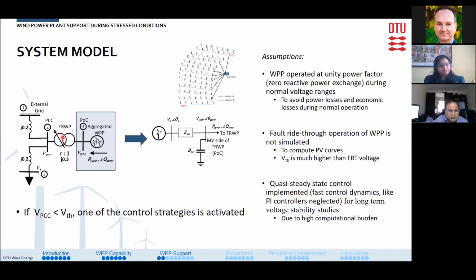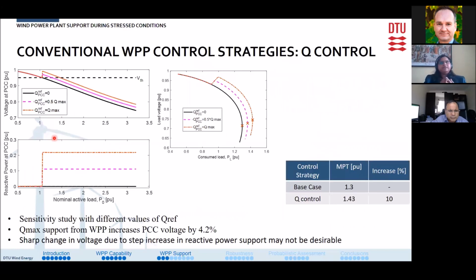Now, the voltage at the point of connection of WPP is maintained by the tap changing actions of the wind power plant transformer. Typically, it is maintained at 1 pu, and the PCC voltage is being monitored in order to detect stress in the system. So when the PCC voltage goes below a predetermined threshold value, one of the control strategies is activated. Firstly, we look into the conventional wind power plant control strategies as described in the grid codes: reactive power control, voltage control, and droop control.